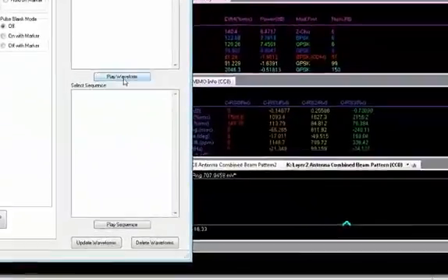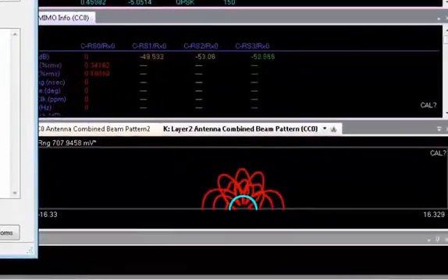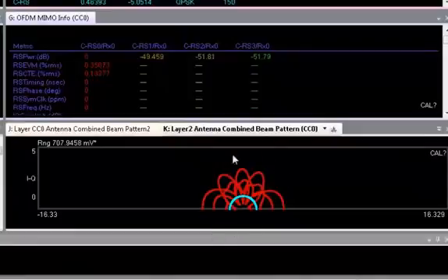We play the waveform and see the non-corrected beam pattern. Variations between the signal channels can greatly impact the accuracy of these beam patterns.